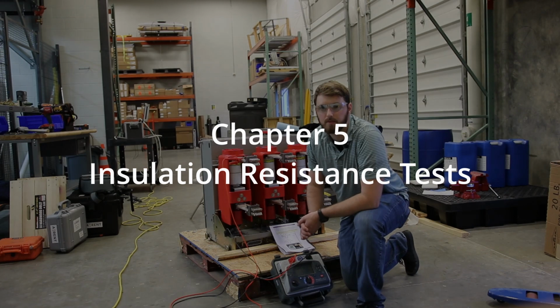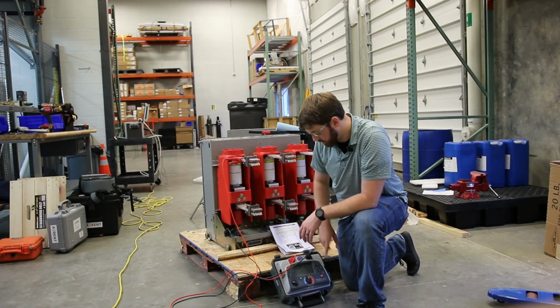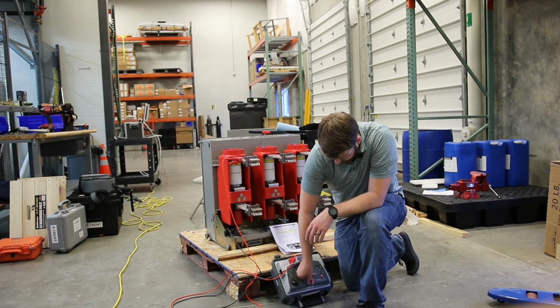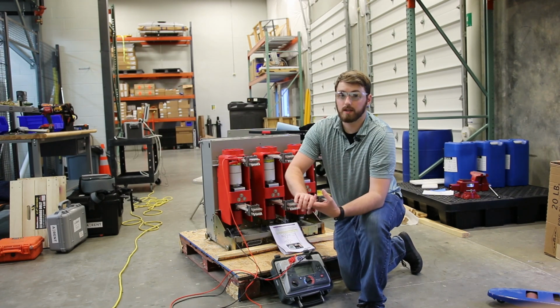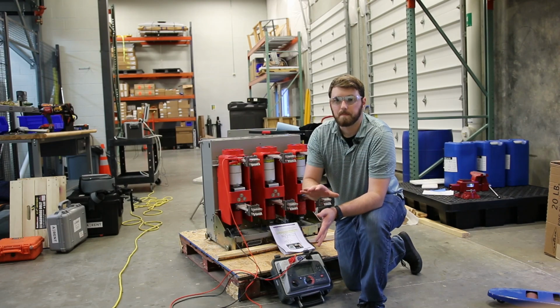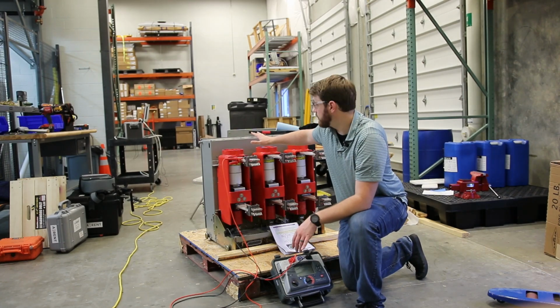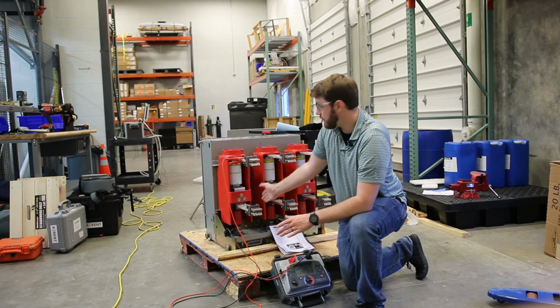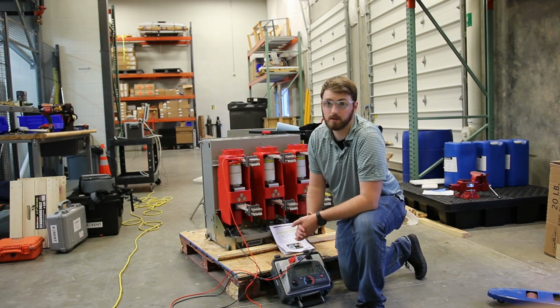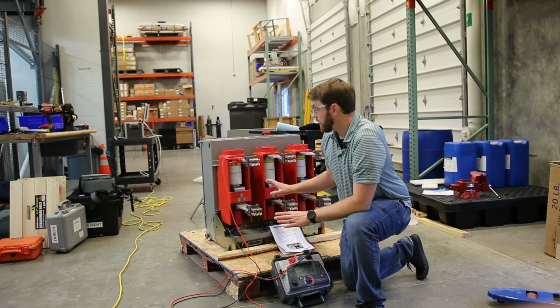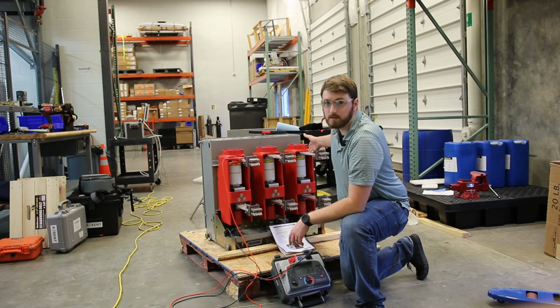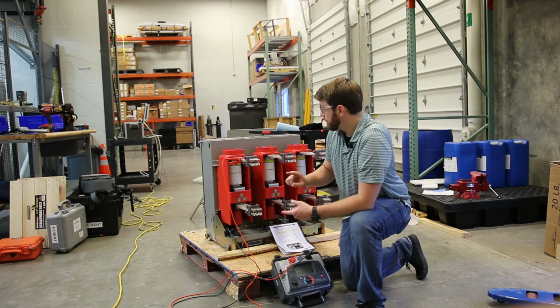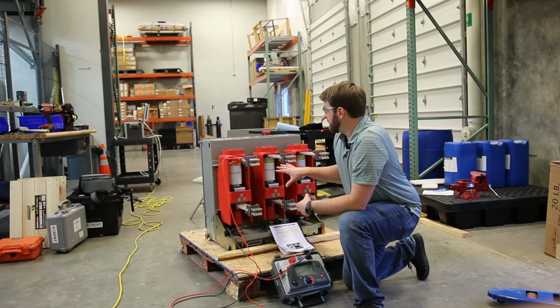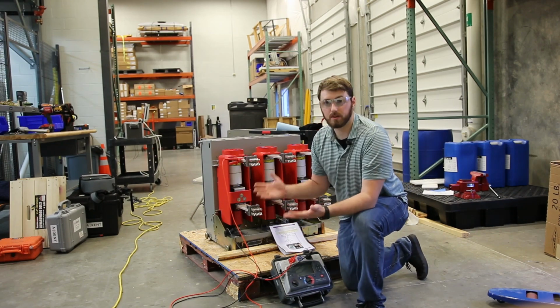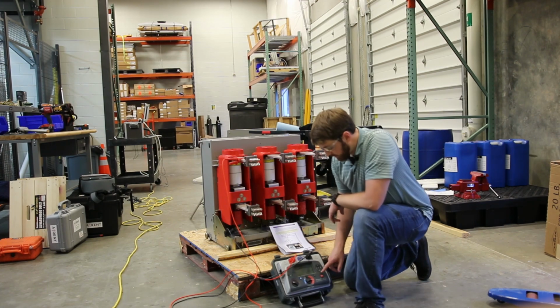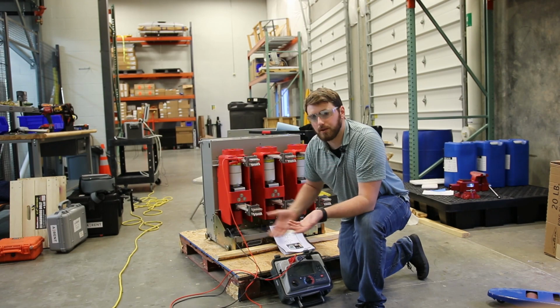All right, this is a 5 kV breaker. So we're gonna test all of the insulation resistance tests we're gonna do with a 5 kV megger set to the 2.5 kV range. We're gonna do 3 distinct tests. Well, it's actually like 9 tests, but we're gonna do 3 different setups. So the breaker's closed right now. With the breaker closed, we're gonna do A phase to ground, B phase to ground, C phase to ground. We're gonna do that for 1 minute. And then with it still closed, we're gonna do A phase to B phase, B phase to C phase, and then A phase to C phase. So we're gonna do each phase to the chassis, essentially. Each phase to the other phases, and then we're gonna open the breaker and we're gonna megger across the vacuum bottle. So we're gonna do each test for 1 minute, winds up being 9 total minutes of test.